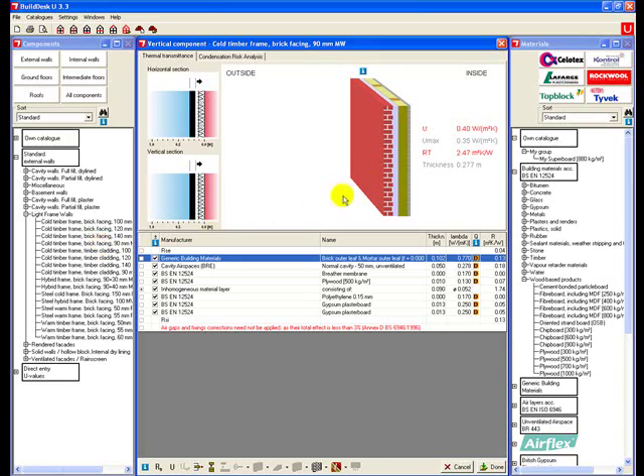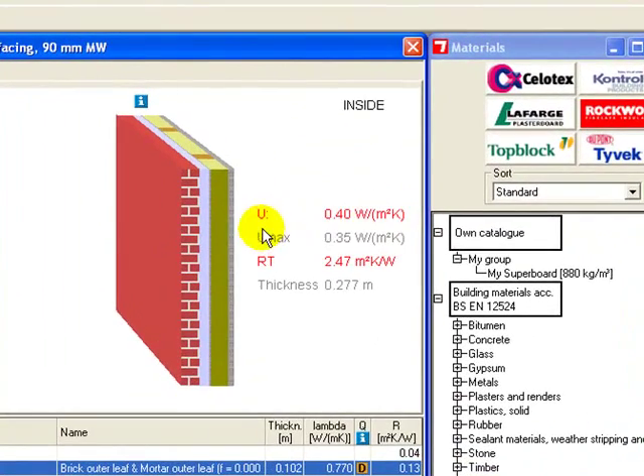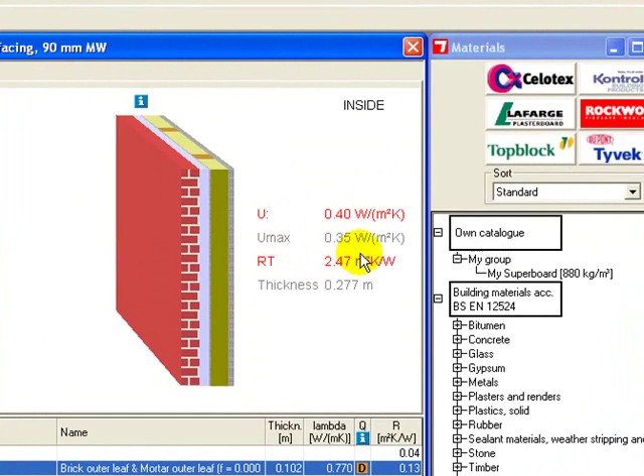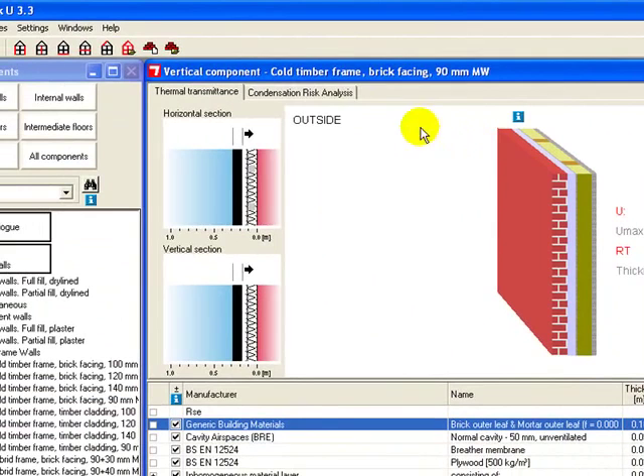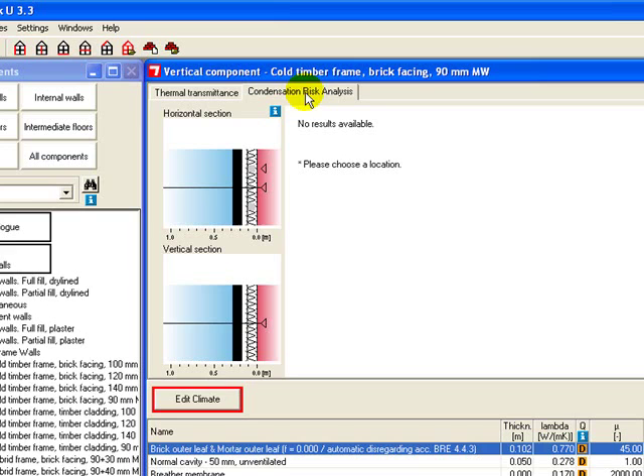Now it's loaded, you can see that the U value is actually greater than that allowed by current building regulations in England and Wales, so this would not be acceptable in England and Wales. If we look at the condensation risk analysis here, we just click on this tab.